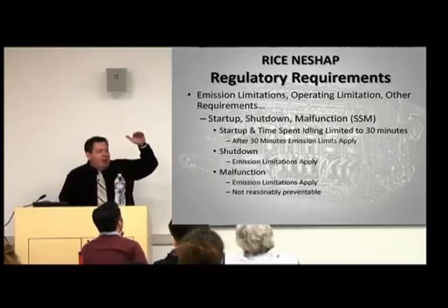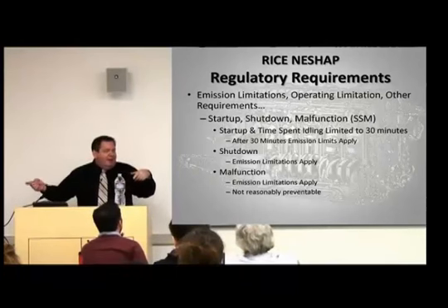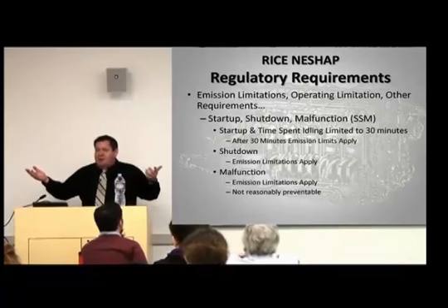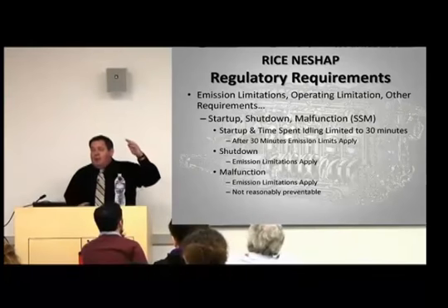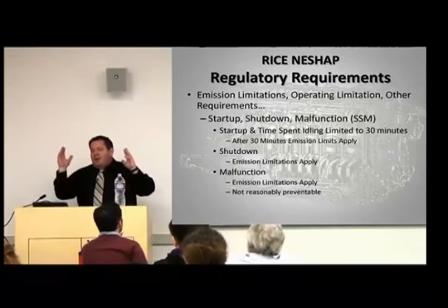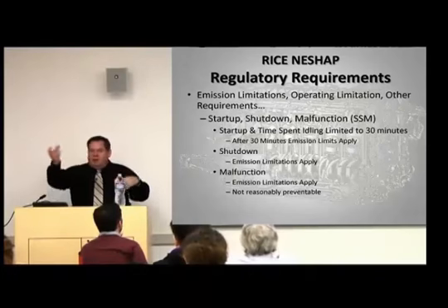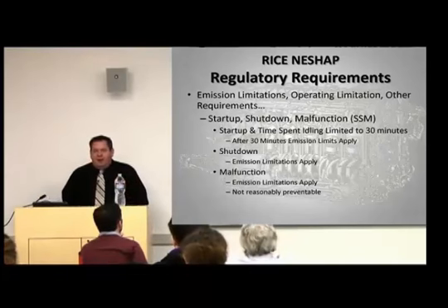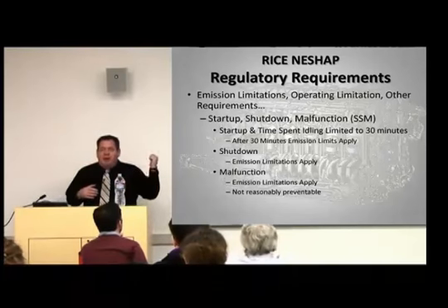Typically it's not a problem because your catalyst stays hot. It doesn't cool off instantly. So as long as your catalyst is up to temperature, chances are astronomically high your emissions are under control. But they can't just take the load off the engine, dethrottle it, and walk away and go have lunch. They have to do it in such a manner that they're meeting the emission limits during shutdown.